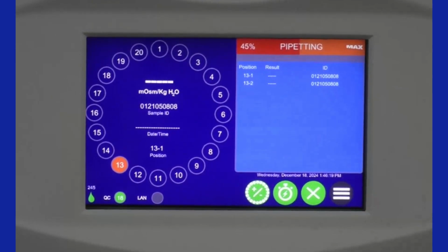And the difference between those is going to indicate to them whether or not it's likely that the patient ingested this toxic alcohol, ethylene glycol, and whether or not they're at risk for permanent organ failure or even potentially death if it goes untreated. So if that gap, that osmolar gap between the measured result that you'll get off your advanced instruments osmometer and the calculated result that you'll get off your chemistry analyzer is greater than 10 milliosmoles, then the provider has evidence to support his suspicion that his or her patient has ingested a toxic alcohol.